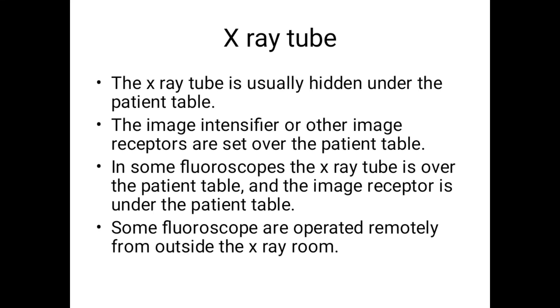Now let's discuss the components of the fluoroscopy machine. We have a fluoroscopy machine made of different parts organized together as a complete unit. The first important component is the X-ray tube, which generates and produces X-rays. We supply electricity and power to it. It is the main component of the fluoroscopy machine.